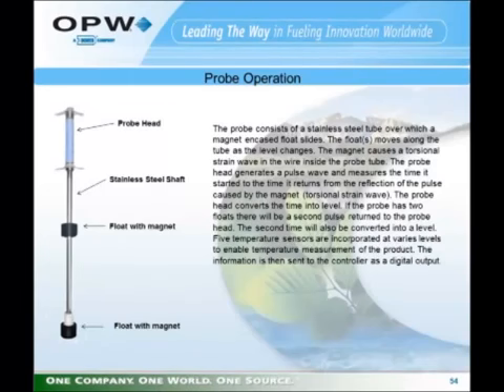Probe operation. Magnetostrictive probe, in simple terms, means that the circuitry in the head of the probe sends a signal down a wire that's going down the center of the probe shaft. When that wire sees a magnetic field, a pulse reflects back up to the top of the probe head and is detected by the circuitry up there. Then the main pulse travels the remaining distance of the probe. If there's a magnet down there, it will see that magnetic field and reflect back another pulse. When the initial pulse reaches the end of the probe shaft, it is then absorbed, so there is no reflection.